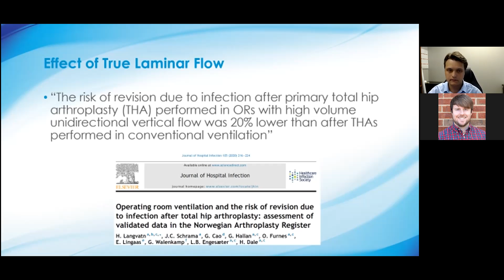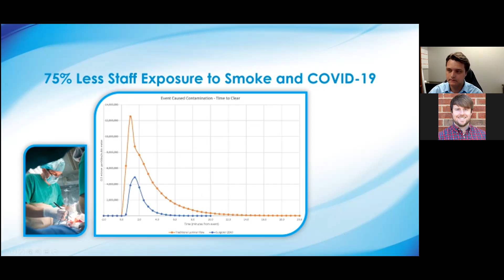I'm short on time, so just quick show you, this system also gives you the ability to rapidly control the temperature of the space. You can heat 10 degrees in 5 minutes, cool 10 degrees in 10 minutes, and that's because we're doing all of this local to the room. We're not relying on the system far away to serve this space. And here's what I was talking about with that dilution of the air, where a traditional contamination event with traditional laminar flow has a huge peak in contamination in the space, takes a full 20 minutes for it to go back down to normal, versus with Surgicare Zero, cuts it down by 75%.